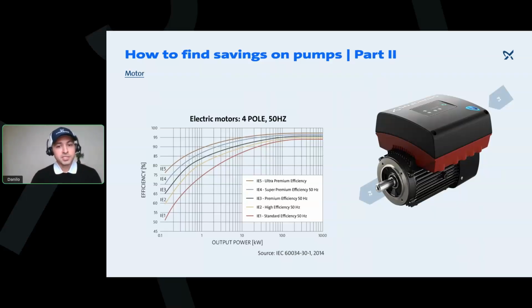Interestingly enough, yesterday I was participating in a training. I was doing an 8-hour course with the Hydraulic Institute about looking at whole systems and how we identify savings. And we did a couple of exercises about how we find savings. One of the exercises was just replacing an existing premium efficiency motor with a super premium efficiency motor. So we gained about 2% efficiency on this motor. And our energy savings at the end, once we calculated, was 0, right? So we just went from one motor to another, running the pump at full speed. What happened is you increase the efficiency of that motor, and that generated a little bit more head, and now you got more pressure. You have more total power consumption in the system. So you win on efficiency, but then you also deliver more kilowatts, and they even out at the end, and we calculated no energy savings, no gains in there.